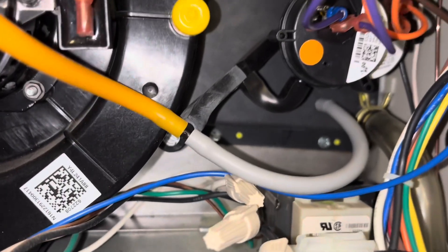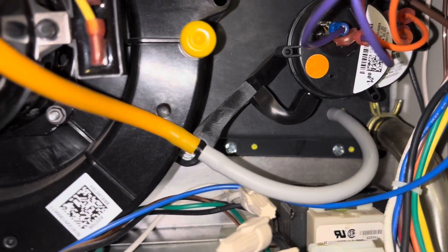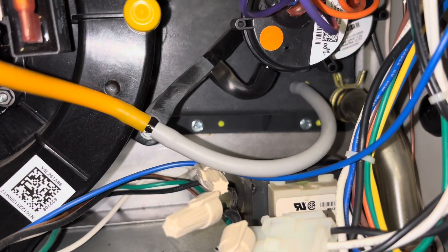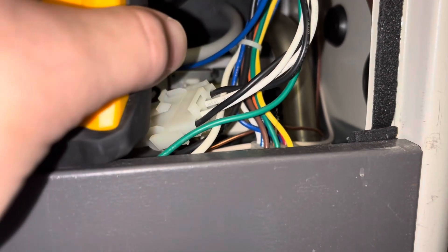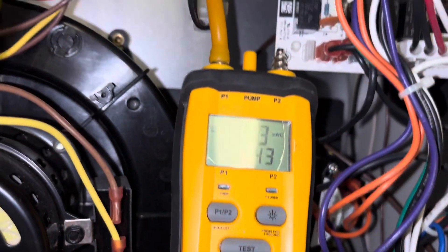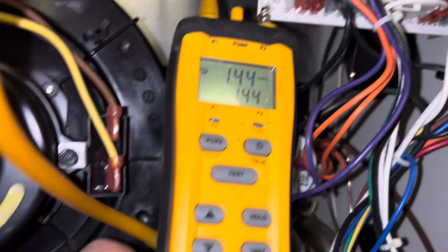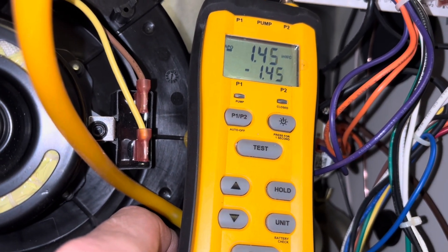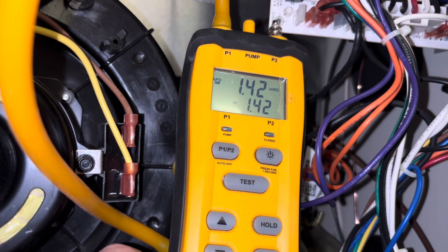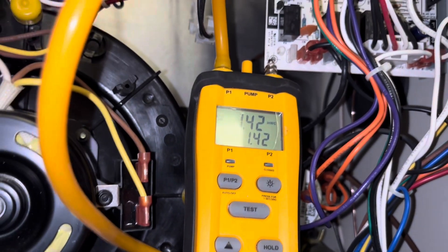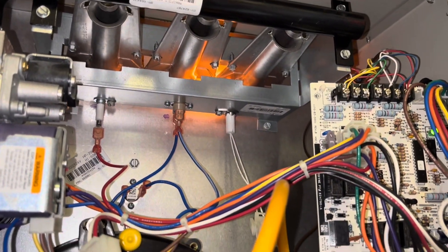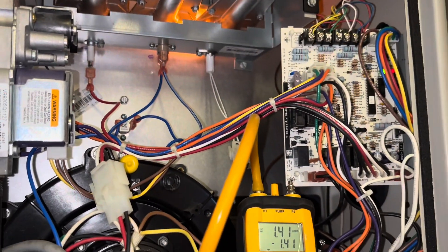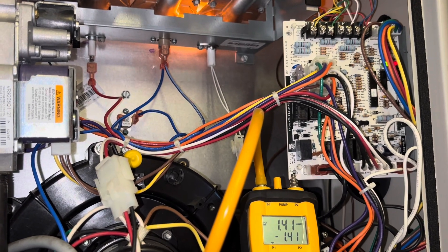Alright guys, we are working on a two-stage Air Temp furnace here, and that pressure switch, the one with the orange dot on it, that was actually bad. I already changed it out, and I'm showing you right here a little T-rig that I made, so the furnace would run, and I could also see how many inches of water column the draft inducer was pulling. So it's running right now, new pressure switch, the pressure switch was bad, it was not making when it hit 1.00 inches of water column. So we changed it out, and I'm firing it up now, just making sure I check over everything.